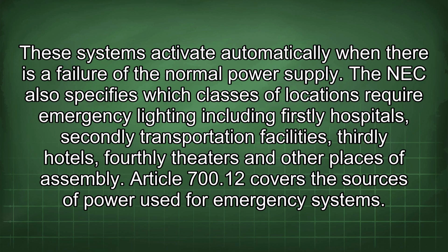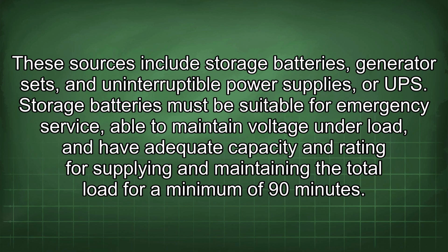Article 700.12 covers the sources of power used for emergency systems. These sources include storage batteries, generator sets, and uninterruptible power supplies, or UPS. Storage batteries must be suitable for emergency service, able to maintain voltage under load, and have adequate capacity and rating for supplying and maintaining the total load for a minimum of 90 minutes.